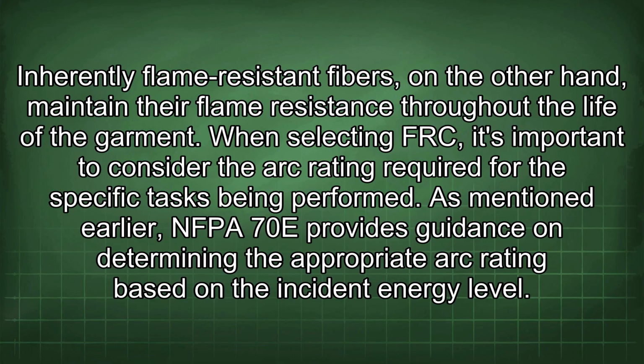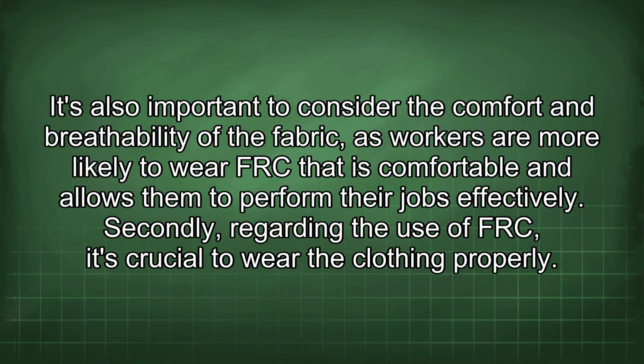When selecting FRC, it's important to consider the arc rating required for the specific tasks being performed. As mentioned earlier, NFPA 70E provides guidance on determining the appropriate arc rating based on the incident energy level. It's also important to consider the comfort and breathability of the fabric, as workers are more likely to wear FRC that is comfortable and allows them to perform their jobs effectively.